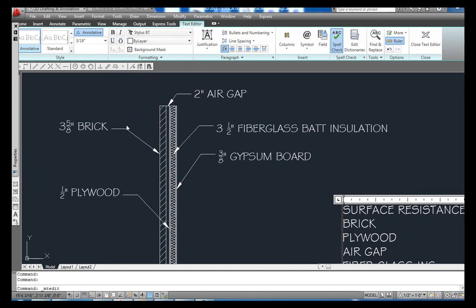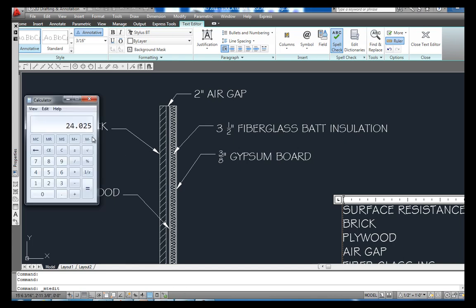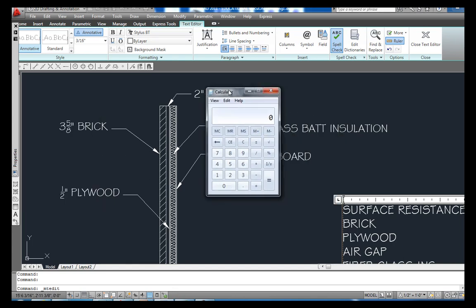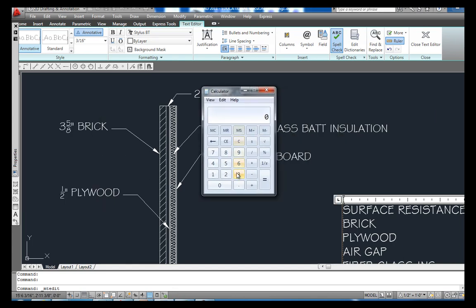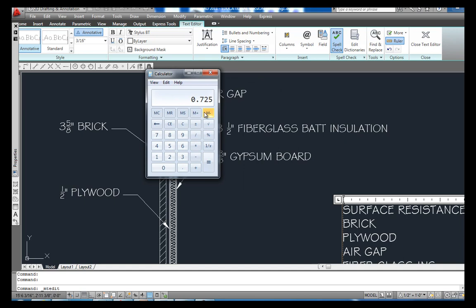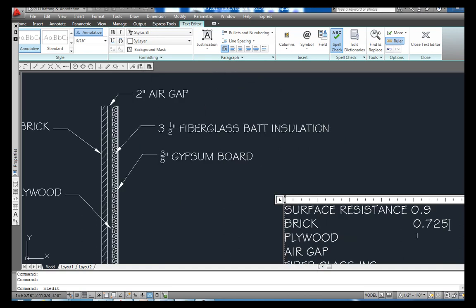Next thing I want to do is look at my brick. It's clay brick, and you can find that, and it is 0.2. I'm finding that in my charts in your book on page 107. All I do is grab a calculator, clear it out. 5/8 is 0.625, so it'll be 3.625, and I want to times it by that R-value which was 0.2, and the R-value of that brick is 0.725. Probably thought it'd be more, didn't you?